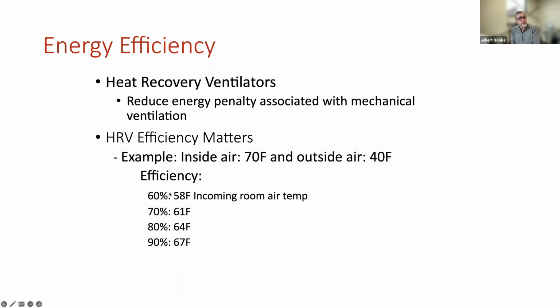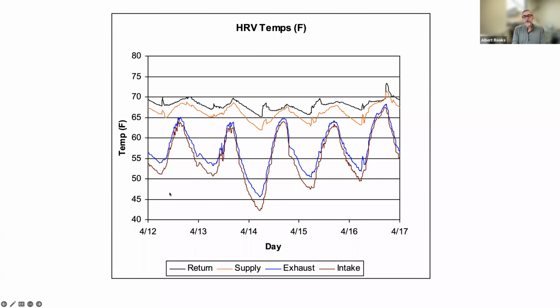So as you increase that from 60% to 70% to 80% to 90%, the airflow warms. And as the airflow warms at 90%, it's 67 degrees. 67 degrees on your skin on a 40-degree day doesn't feel so bad. That's not something that's going to make people uncomfortable. And it's a much, much smaller energy penalty. And from an energy standpoint, you know, how far you can take these things in existing buildings and new constructions is this building right here, which was built in Washington State, and it was monitored by University of Portland.